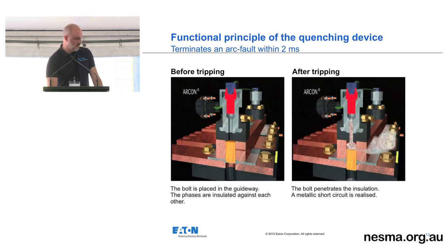So you'll see there, the action or the quenching principle is before the trip, you've got a bolt which is placed in the guideway, all the phases insulated against each other. After the trip, after the actuation occurs, that bolt penetrates the insulation and a metallic short is realised.